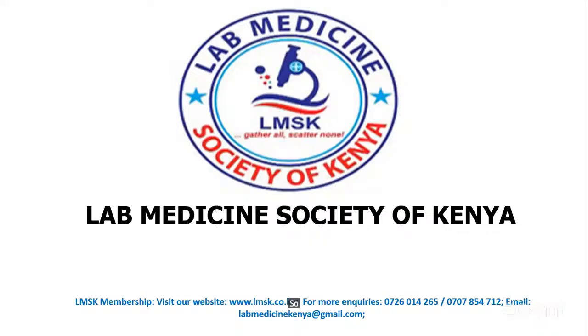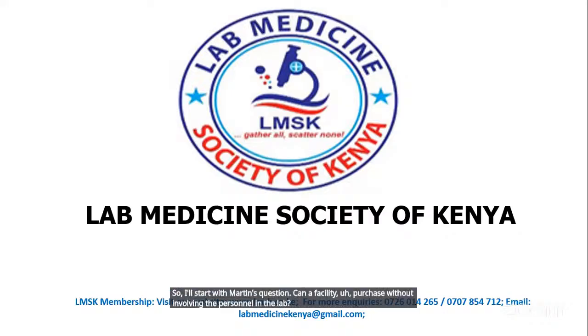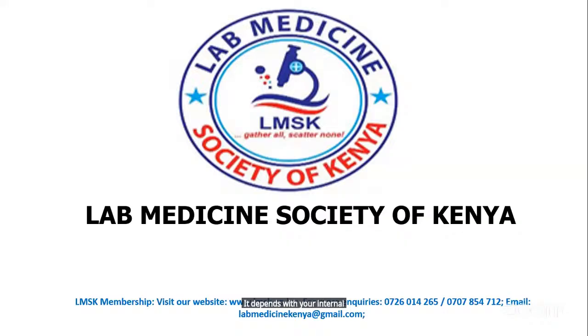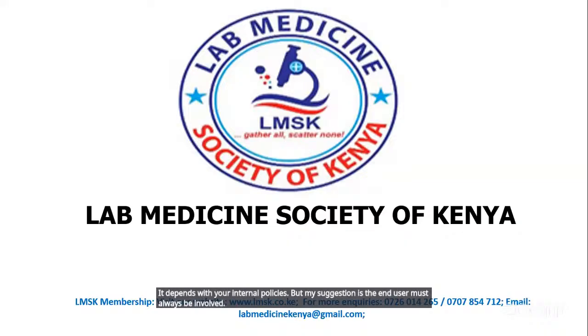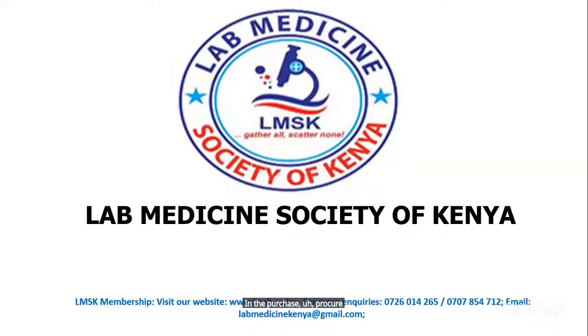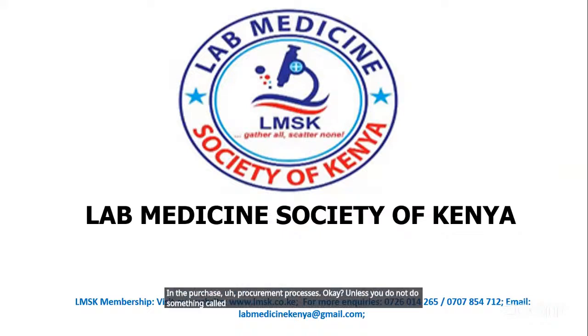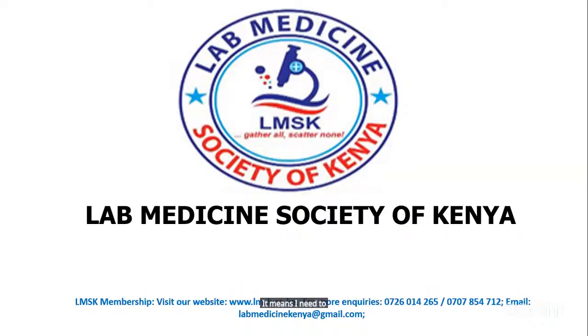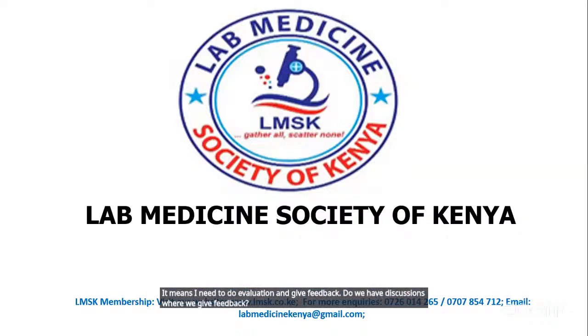So I'll start with Martin's question. Can a facility purchase without involving the personnel in the lab? It depends on your internal policies, but my suggestion is the end user must always be involved in the procurement processes, unless you do not do something called supply evaluation. Because if you do not involve me, at the end of the day, I find that what you brought in is not working. It means I need to do evaluation and give feedback. Do we have discussions where we give feedback in such scenarios?